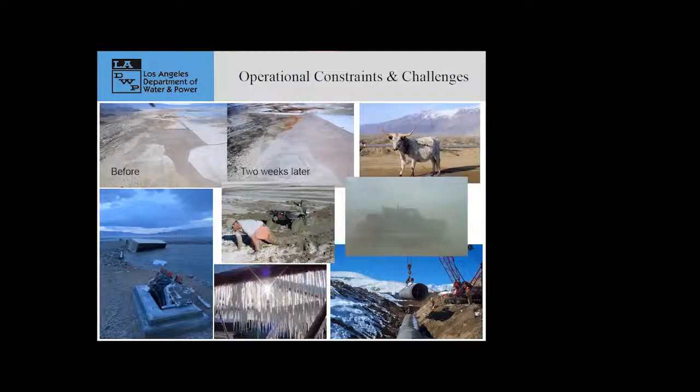But I think to speak a little bit more specifically on those environmental challenges in terms of water. As I mentioned, there's a lot of sediment and organics present in the water that runs through the whole mainline. We have filtration systems that we try our best to filter out the majority of it. But during certain times of year, if it's really hot, we find that stuff is making it past that and continues on through our conveyance system, and then it causes issues out in the field. Also, with the salts that are naturally occurring in that water, we find that in some of our piping, especially the plastic irrigation piping that we have in North Sand Sheet, which was in the first phase, there will be calcium buildup in the lines. Obviously, that's not good. It restricts the flows, and causes pressure losses and affects our ability to get water to the different areas for dust control.